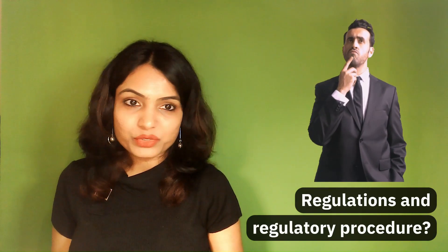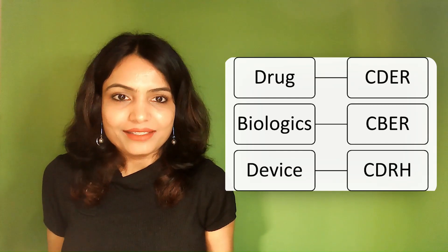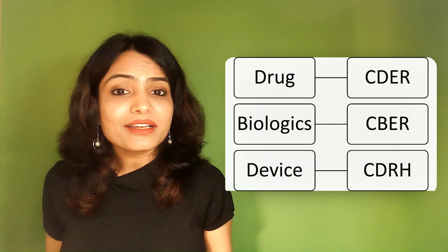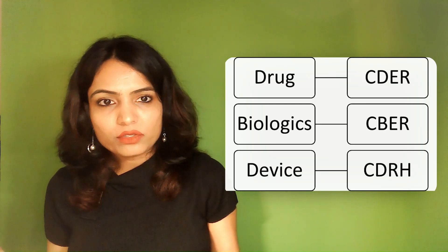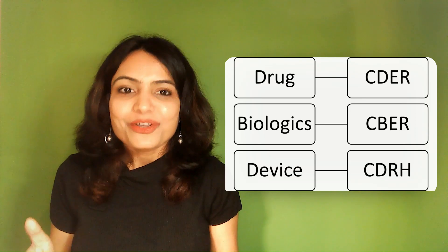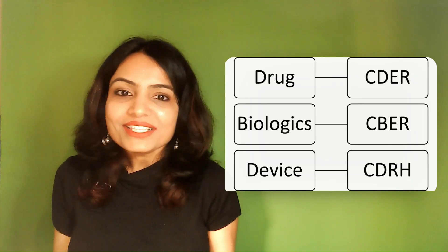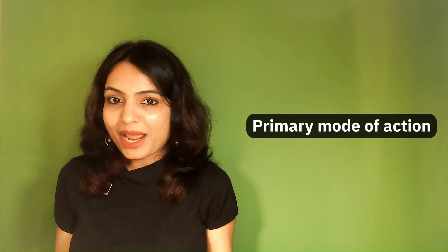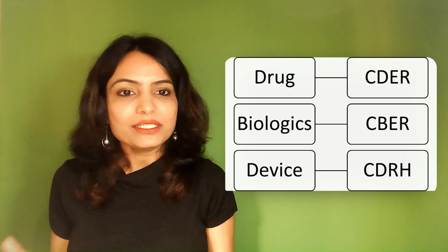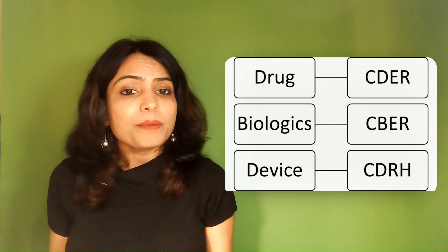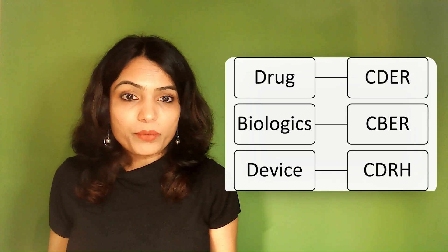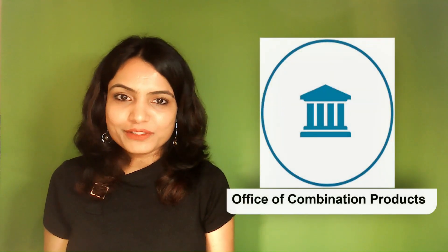Now let's look at regulations for combination products — how regulatory procedures work in the US and EU. In the US, drugs are reviewed by CDER, biologics are reviewed by CBER, and devices are reviewed by CDRH. These are the different centers responsible for reviewing your product. For combination products, which are a mixture of these components, the reviewing center depends on the primary mode of action. If the primary mode of action is a drug, the lead reviewer center is CDER; if biologic, it's CBER; if device, it's CDRH.